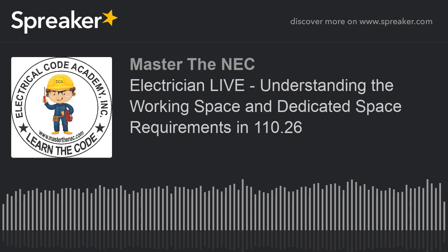So if you're facing the switchgear, panel board, or whatever, that is the live parts emanating out from you. So it's coming out in your face. I like to say, in your face. Okay? Shall not be less than that specified in table 110.26A1. You'll notice there's a little table. If you're in the softbound edition of the 2020 code, it's on page 50. Okay? It'll help you out there.